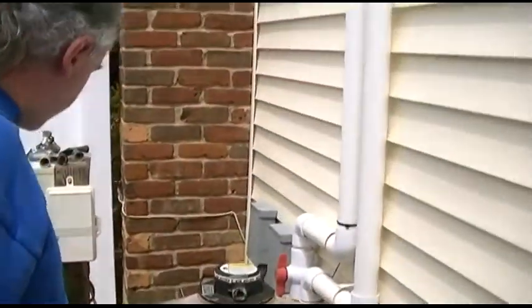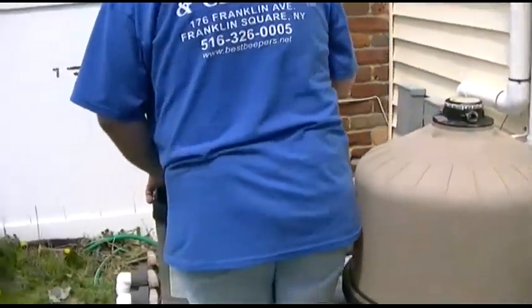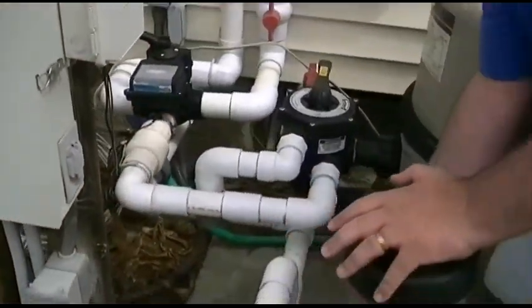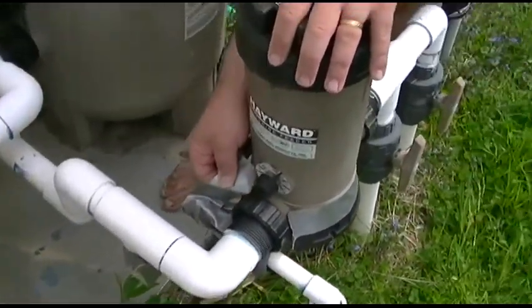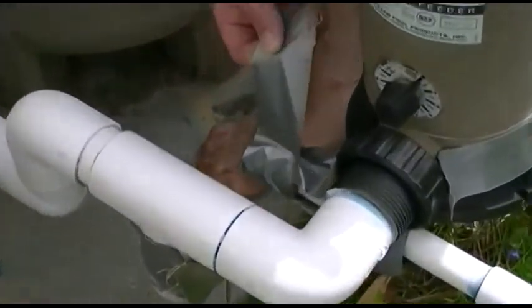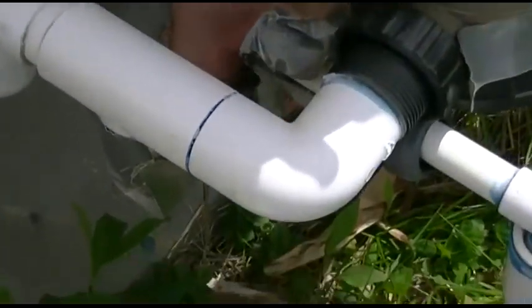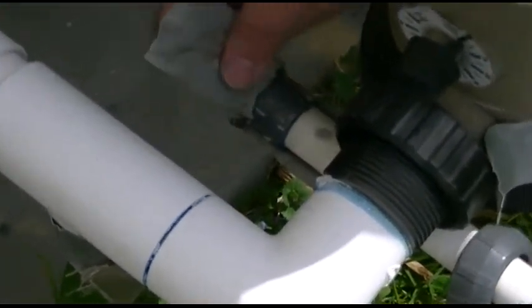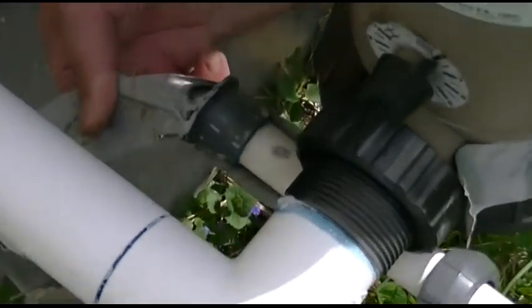Now I gotta put the gauge in there when we get to it. And if you want to come around over here, we have the other fittings to untape, which again looks like they did an excellent job putting some el cheapo duct tape on. You do want to be very careful when pulling this off because these are unions and they should have O-rings in half of them.